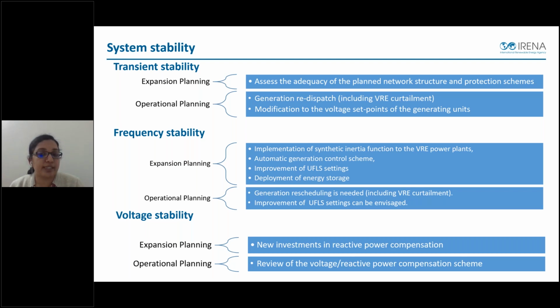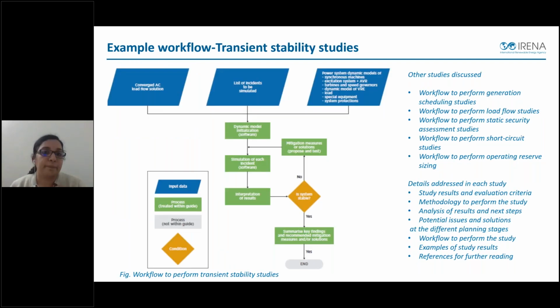And in case of voltage stability, expansion planning would be to consider new investment in reactive power compensation devices, whereas in case of operational planning, it would be to review the settings of the reactive power compensation schemes which are already implemented. So next slide, please. Next slide.